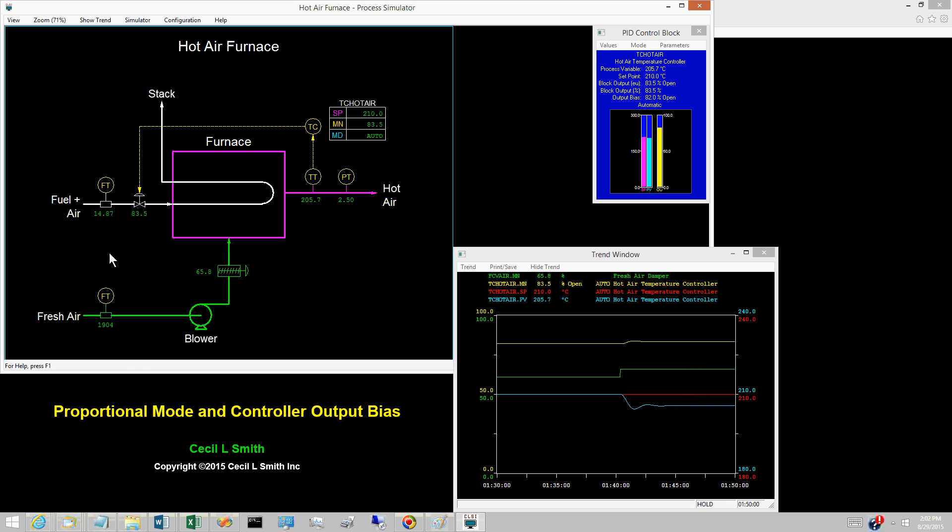The amount of fuel that must flow to the furnace depends on the fresh air flow. In this sense, the fresh air flow is the load on the furnace. For proportional only control of the hot air furnace, an increase in the load causes the hot air temperature to droop down.